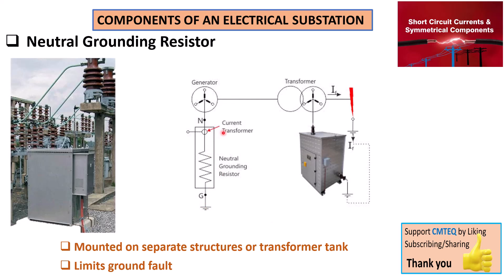Because if the current transformer is no longer able to detect the fault current, you are basically defeating its purpose and rendering your system unreliable. The system still needs to remain reliable by being able to detect fault current and interrupt it so that technicians can attend to the fault. Before you place a reactor here, you must ensure the new fault current value will still be within the margin for the current transformer to operate.